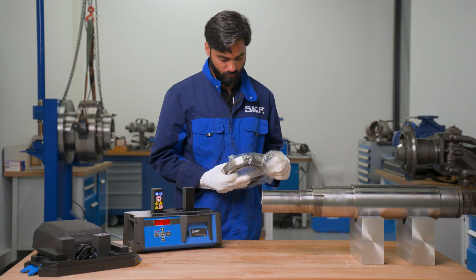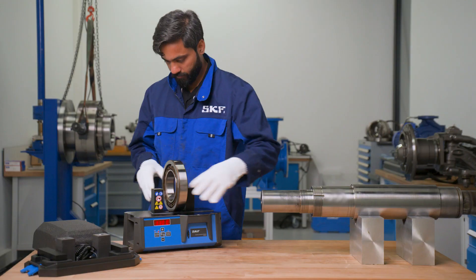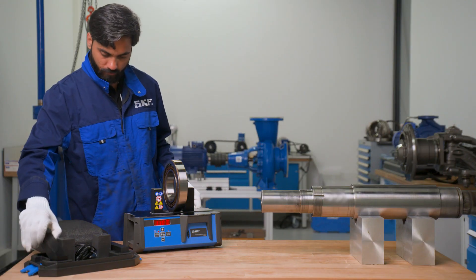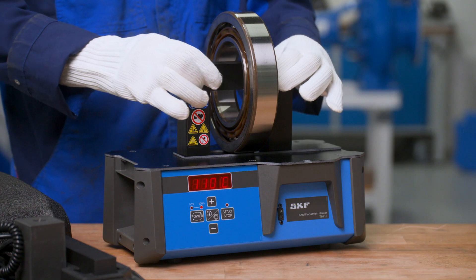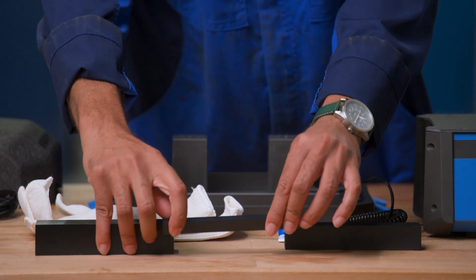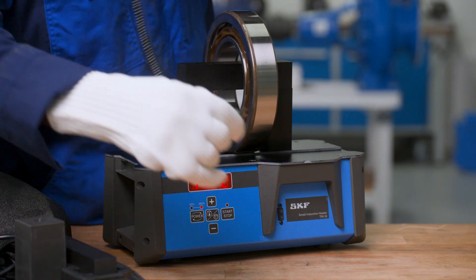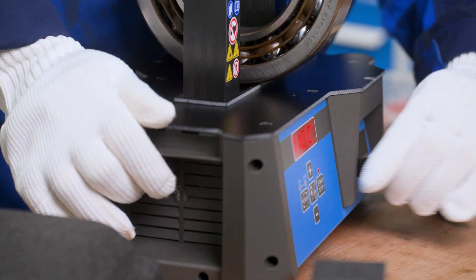To use it, place the workpiece between the vertical supports and rest the yoke on top to complete the conductive circuit. For smaller workpieces, smaller yokes can be found in the dedicated tray compartments. Finally, place a temperature probe if you wish to heat to a desired temperature.